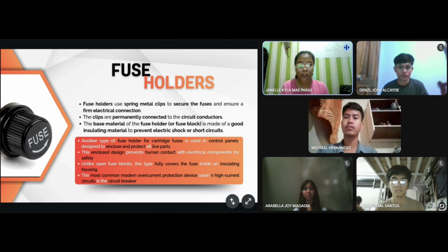Next is fuse holders. A fuse holder is a device that uses spring metal clips to secure fuses and ensure a firm electrical connection. The clips are permanently connected to the circuit conductors, while the base material of the fuse holder or fuse block is made of good insulating material to prevent electric shock or short circuit.